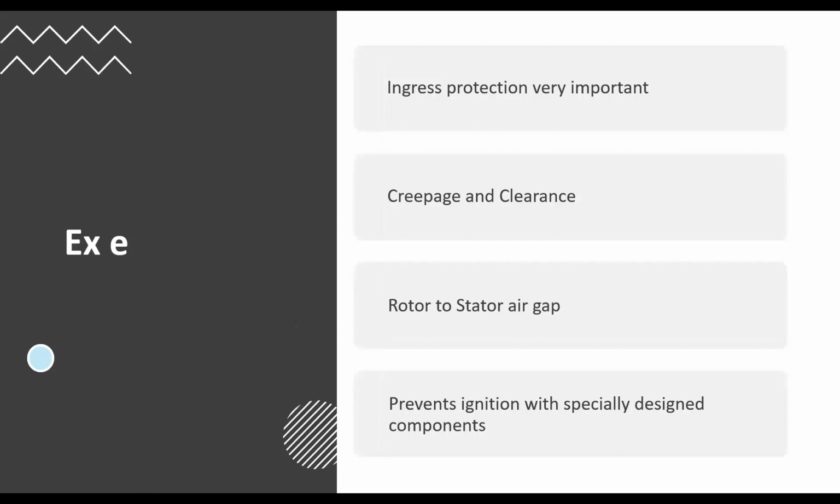Ingress protection is very important. If you think about it, you don't want conductive dust or moisture getting into the terminal box of an EXE, because it is designed never to arc or spark. Creepage and clearance: creepage is the tracking from one terminal to another across the base of it. Clearance is the tracking in air. So again, if you had conductive dust inside there, the clearance could be reduced.